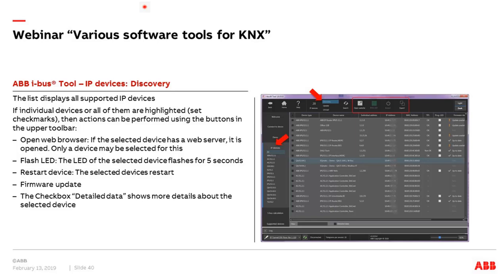Inside the i-bus Tool is also the discovery tool, which scans the IP network and shows all KNX IP devices such as IP routers, application controllers, telephone gateways. The list shows IP address, MAC address, KNX twisted pair status, and firmware version. You can tick a device and click Flash LED to flash its LED for identification in a distribution board. A checkbox shows more detailed data including firmware details.